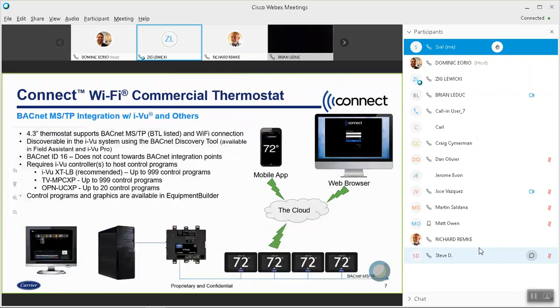In the case of the 4.3, it is a BACnet thermostat. It's BTL listed. It is discoverable using BACnet discovery with our tools, like, for example, Field Assistant, i-Vu Pro, or any other BACnet tools that do that type of function. It's BACnet vendor ID 16, which is Carrier. So that means any of the BACnet points that are discovered do not count towards any limits that we have in our controllers.